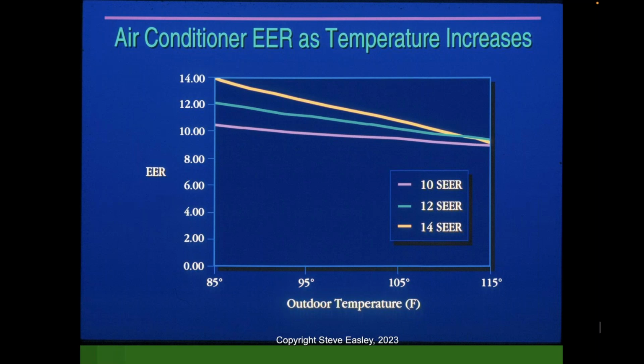Now, for those of you that might be viewing in from the West, when I talked earlier about why EER versus SEER, this is a good example. Let's just say we have a SEER 10, 12, and 14 piece of equipment. That's what we're looking at here. And 85 degrees will be SEER 10, 12, and 14. But look what happens as the outdoor temperature gets warmer.